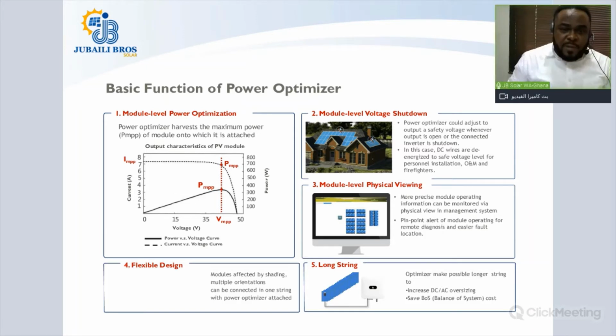The final basic function is to offer long string design. This allows us to oversize the DC-AC ratio larger than the traditional string design. So instead of, let's say, a maximum of 19 PV modules in a string, with the PV optimizers we are able to do much more than 19 PV modules in a string. And how we are able to do that is part of the slides that I'll be explaining.